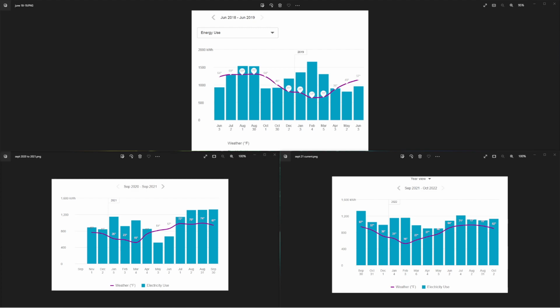That being said, what this guy was kind of hinting at was if you have 2 or 3 smaller units rather than one bigger unit, maybe the condenser doesn't have to kick on as much, because the units that need to be on are on one condenser, and the units that aren't operating are on the other condenser, and you can kind of regulate temperature that way.